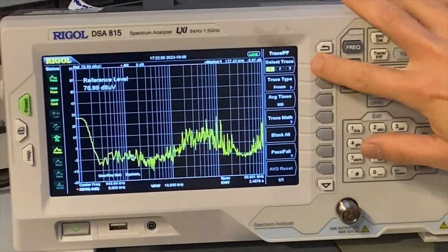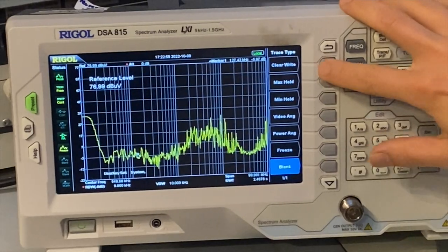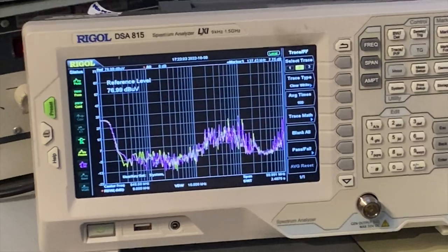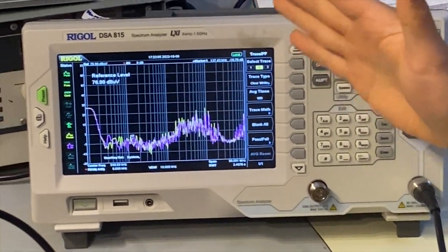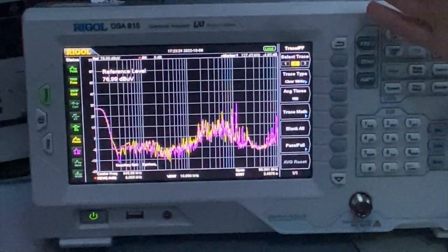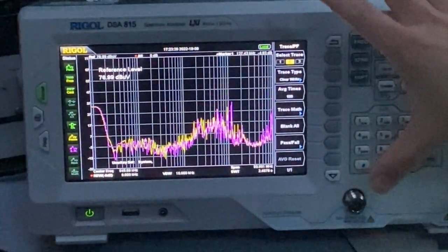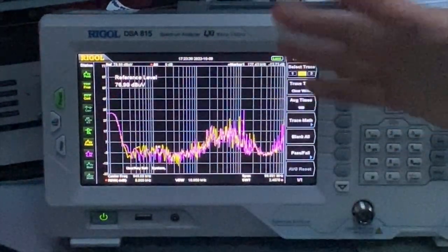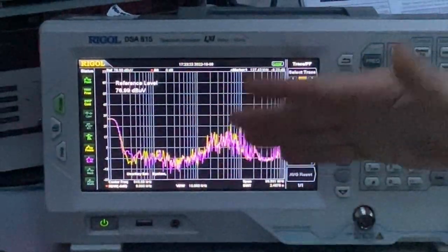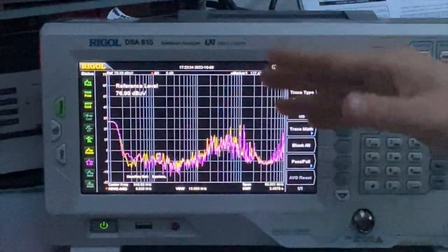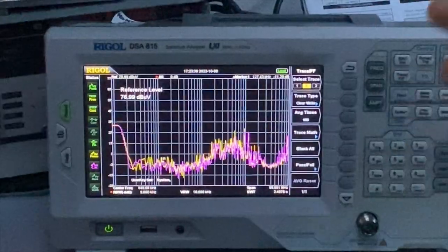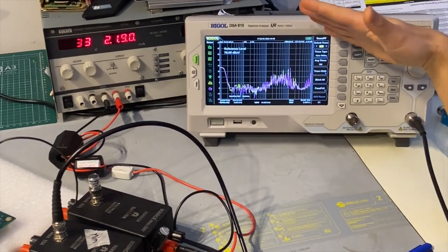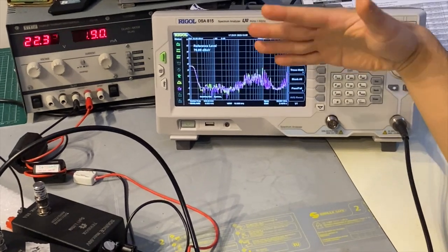And then we use another trace, trace 2, to see the impact of the LED lights. So I'm going to switch off the lights and see what happens. As you can see, now the lights are completely off. But the noise is more or less the same, which indicates the LED lights are good quality. They don't really radiate much. That's a good sign. So at least we can switch the lights back on again. So it is not the radiation from the LED lights.